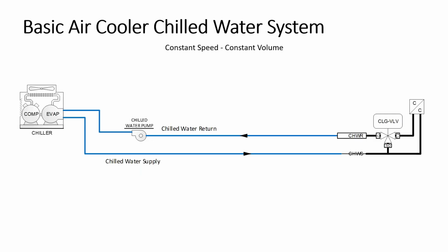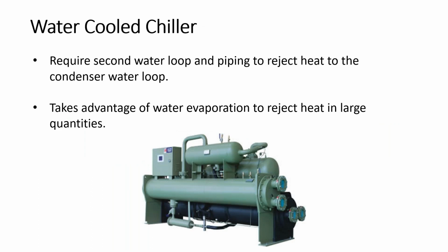It's a fundamental system. This is a constant speed, constant volume system using an air-cooled chiller. In a constant speed, constant volume system, you've got to keep the flow up. So we use three-way valves on all of our cooling coils. In other words, the valve either puts the water to the coil or it has to bypass and mix going back to the chiller to keep the flow up in the system. So these were typical of systems 20, 30 years ago, before the advent of variable speed. So we talk about water cooled. It required a second loop to pipe up the condenser water loop. It takes advantage of the evaporating effect of water to reject heat in large quantities.